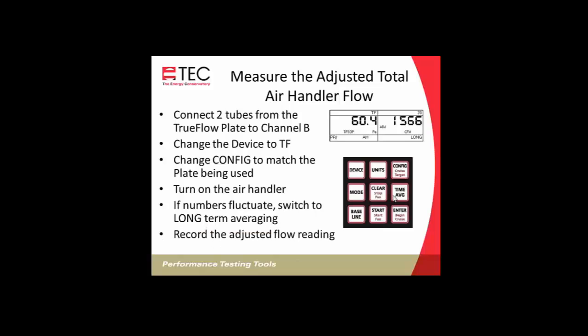So we'll record our adjusted flow reading. And the reading that's being displayed, you see it says ADJ here. And that means it's making the adjustment for the difference between normal system operating pressure and TrueFlow system operating pressure. It's automatically making those adjustments. You don't need to look on the charts or figure that adjustment factor. It's doing it automatically. And the flow you're reading is the adjusted flow.